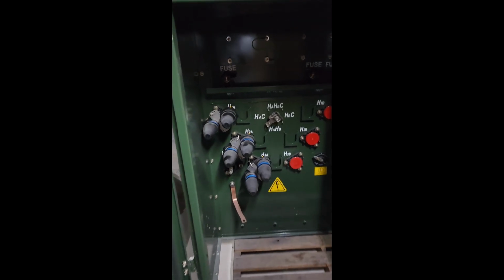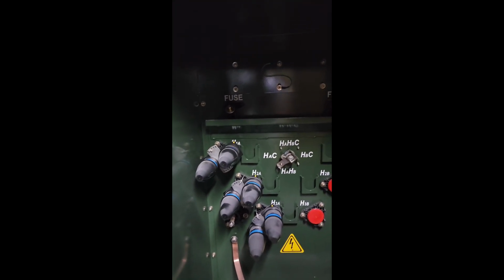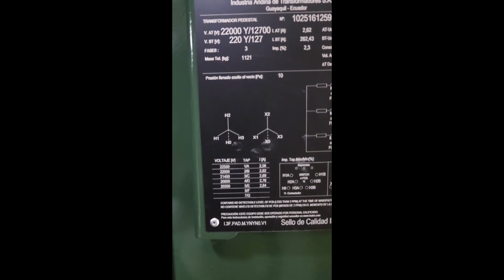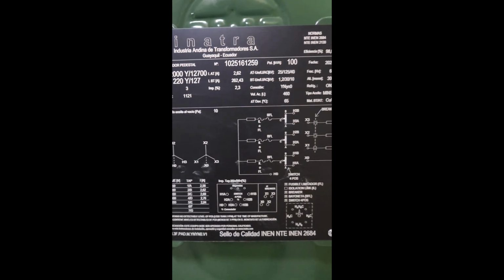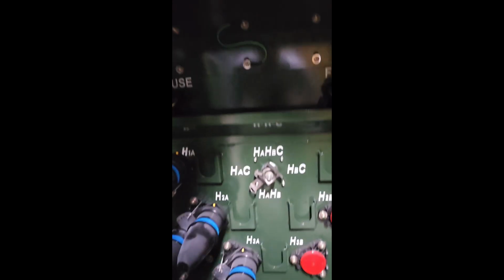Let's take a look at this high voltage transformer, 22,000 volts primary, Y primary to a 220/127 secondary Y. Take a look at this. So here we have the primary side, and here we have the secondary side. And we can see it's Y input and Y output. This is a 100 kVA transformer.